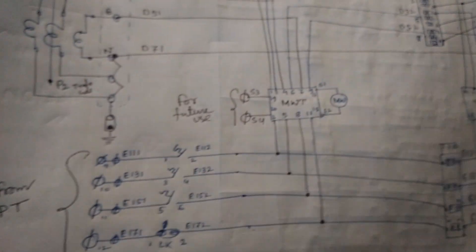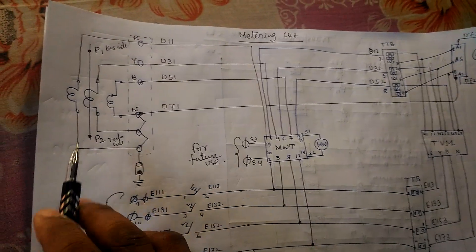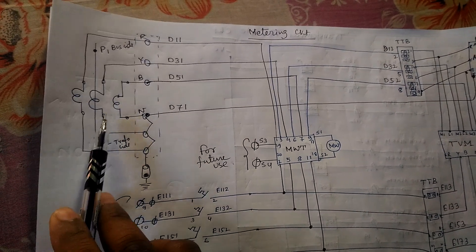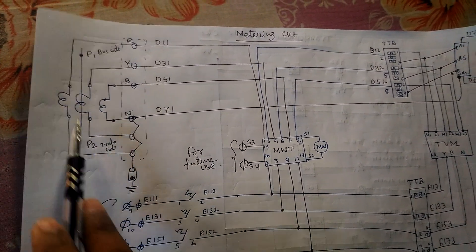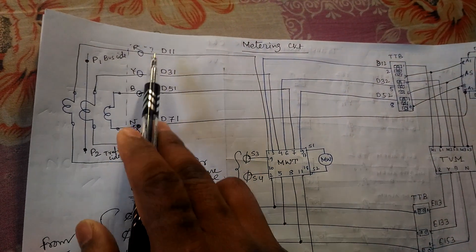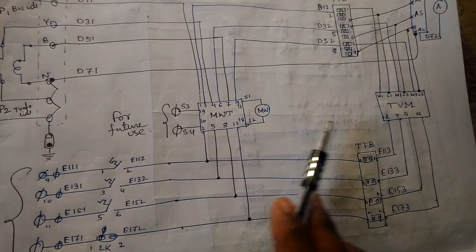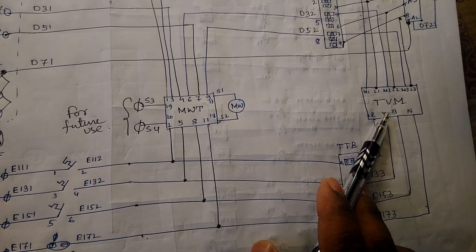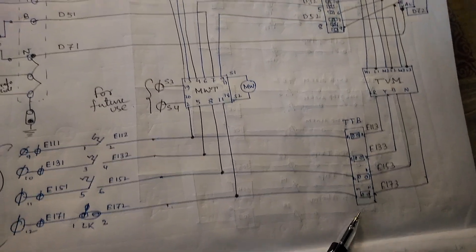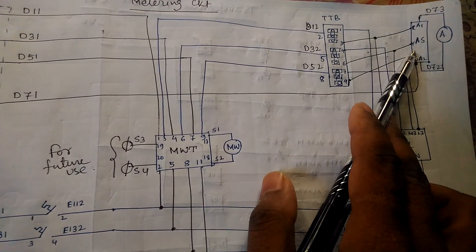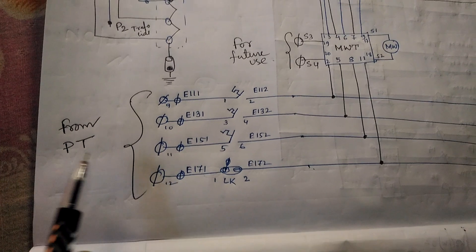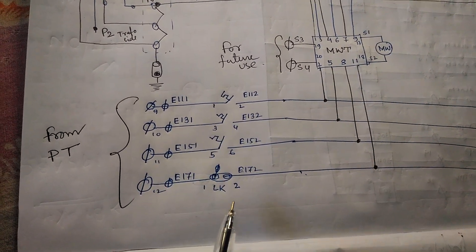Now we discuss the first topic: the metering circuit — how we connect the metering circuit in a panel. The CT has three cores: 1S1, 1S2 for each phase — R, Y, B. This is the megawatt meter, this is the TVM (trivector meter), this is the TTB (test terminal block), and this is the ammeter selector switch and ammeter.